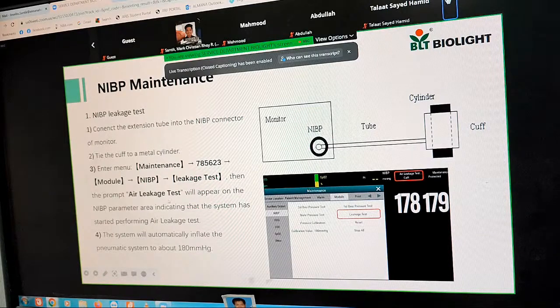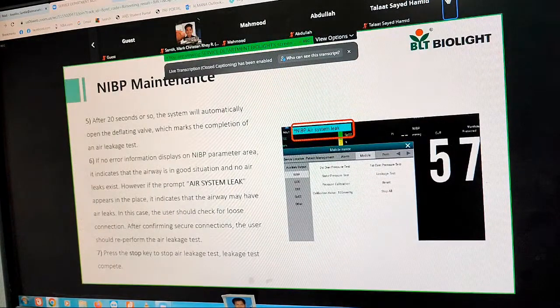Then the prompt "air leakage test" will appear in the NIBP parameter area, indicating that the system has started performing the air leakage test. The system will automatically inflate the pneumatic system to about 180 millimeters of mercury. After 20 seconds or so, the system will automatically open the deflate valve, which marks the completion of the air leakage test. If no error information displays in the NIBP parameter area, it indicates that the airway is in good condition and there is no air leak.